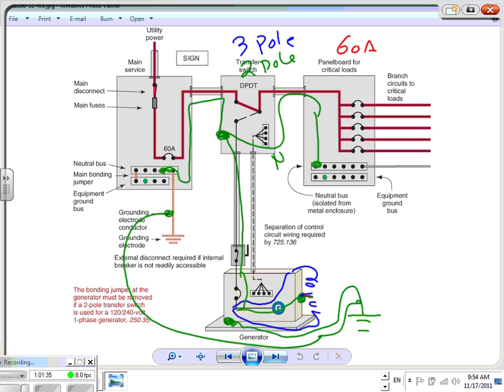If you don't, then you have to have a two-pole switch here, and then look what happens. The question would be, Ashley, Chad, if you didn't ground the neutral here, where would the neutral be grounded? The neutral has to be grounded. Look at that. I didn't ground the neutral here, so keep moving, and you can see that right in here. Keep moving all the way through. Where do you think the neutral got grounded? Right in here. Right in the panel.